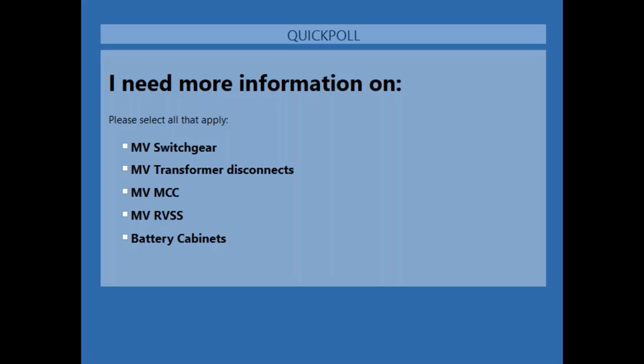The switch itself is available all the way up through 34.5 kV applications, but it does have a lower interrupting rating, but I'll tell you what it does have. It has a higher mechanical rating. Most of those air switches are good before you need maintenance, right? For 100 mechanical operations or 10 load break. Whereas the LBS kit, what you call HVLCC mechanism, the Schneider Electric switch, is 10 times that. So it's good for 1,000 mechanical operations and 100 load break operations.